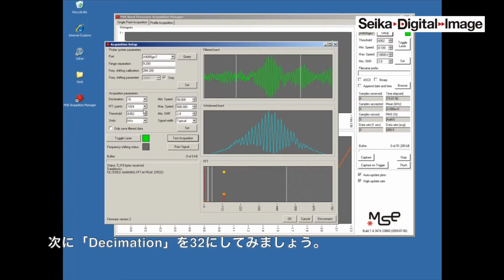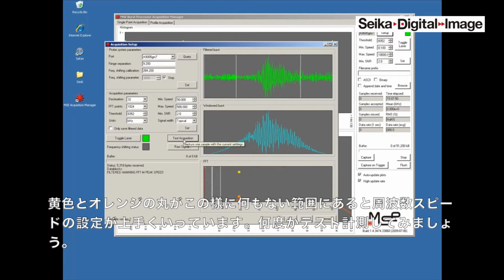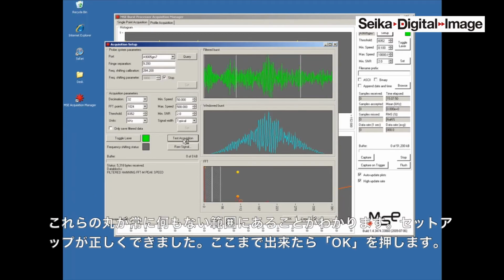We can even go to 32, and let's see what happens when you go to 32. Take another one. Sometimes you have to hit it twice. As you can see, it's quite variable, but it's in this range. And as long as this yellow dot is inside the clear area, your acceptable bandpass is good. We can do it a few times, and you can see the dot is always in the clear area.